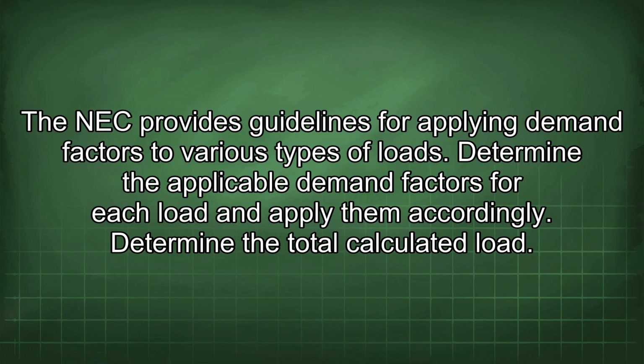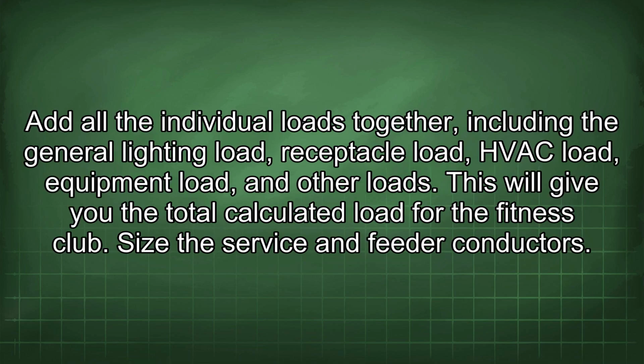Determine the applicable demand factors for each load and apply them accordingly. Determine the total calculated load. Add all the individual loads together, including the general lighting load, receptacle load, HVAC load, equipment load, and other loads. This will give you the total calculated load for the fitness club.